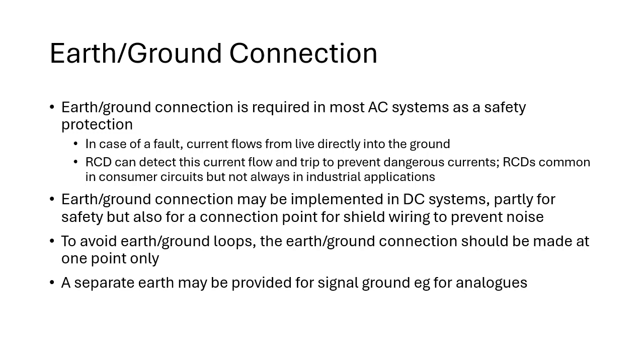Now, in DC systems, you might also have an earth or ground connection. So there may also be a safety implication, although the risk of electric shock from anything below about 40 volts is low, unless you've got very wet skin. But also we might want that earth or ground connection as a connection point for shield wiring to prevent noise. So particularly for analog inputs, you might want to earth the analog shield, and the way that works is the shield receives all the noise, and then all that noise goes straight down to ground or earth without affecting the internal wires which are being used to carry your analog signal.